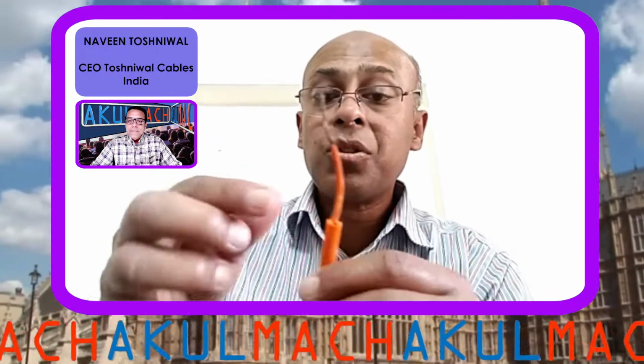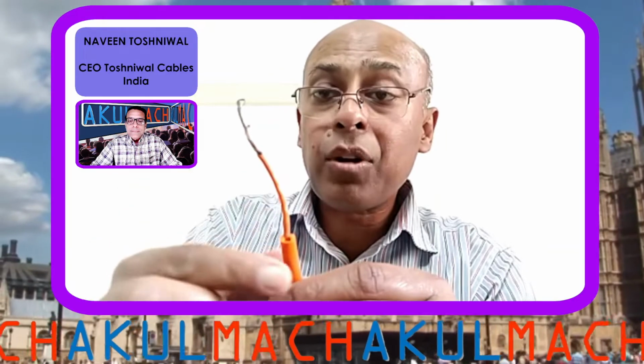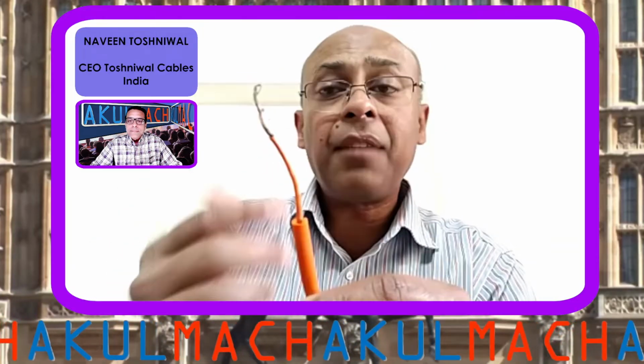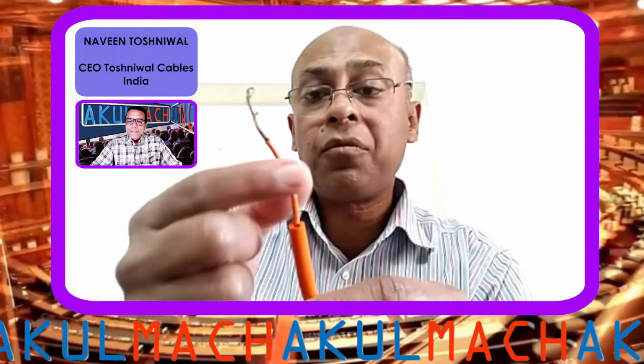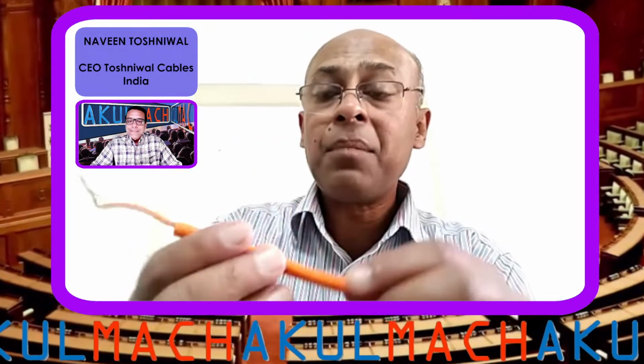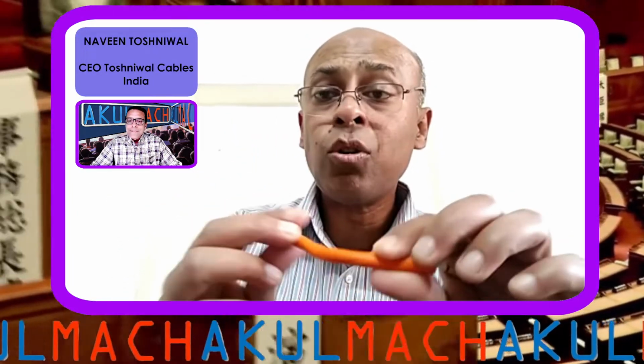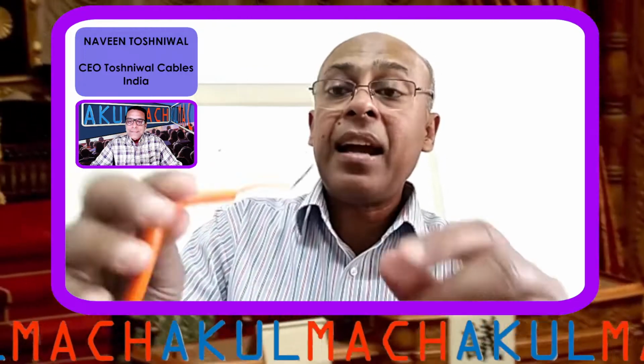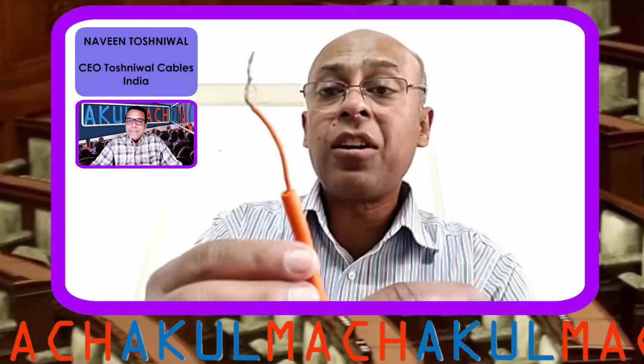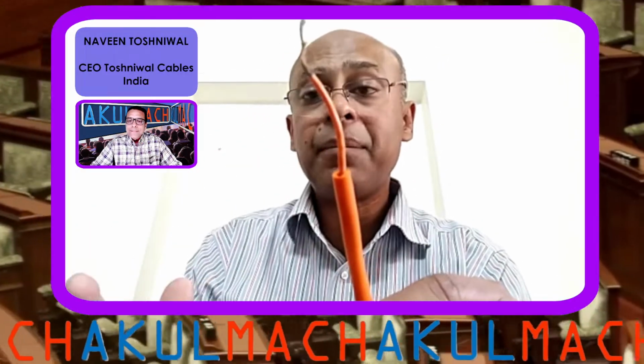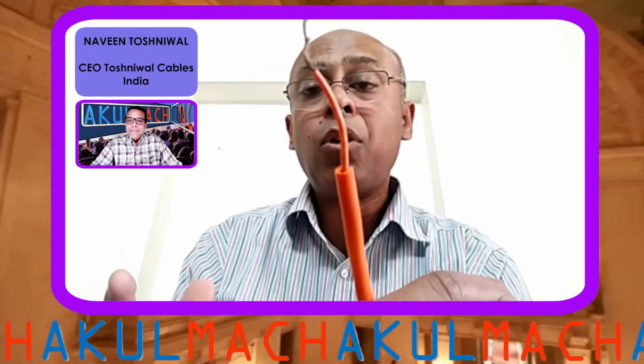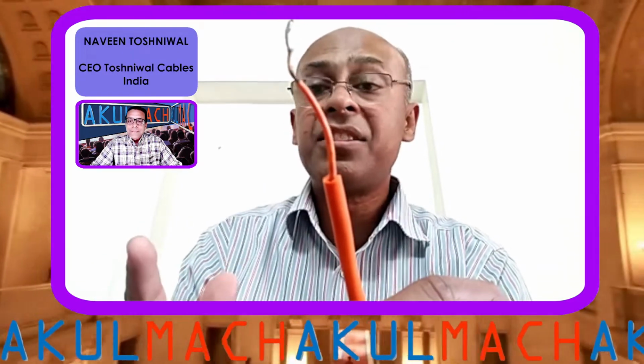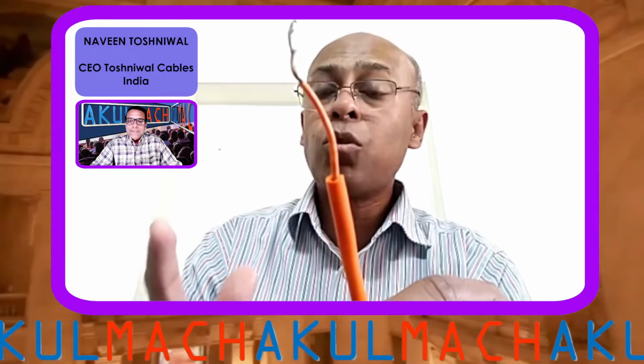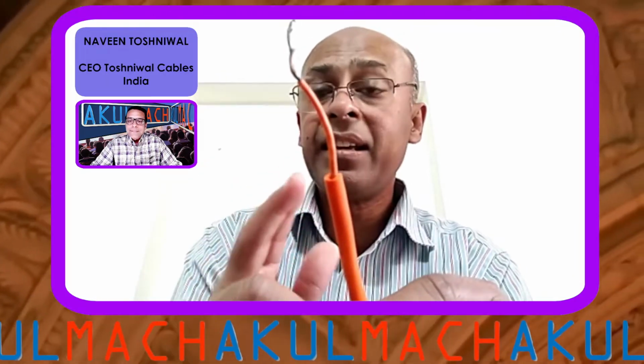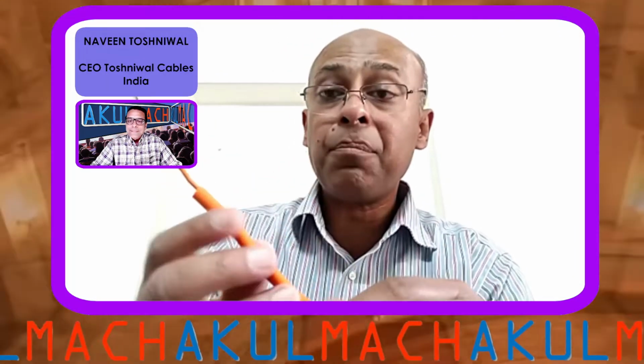So this is one insulation, and for protection, the double insulation is there. Of course, that is as per client's choice if they want one insulation or double insulation. But the most important thing to note here is the flexibility. And another important feature of silicon rubber is that it can withstand temperature of about 150 to 180 degrees centigrade. Of course, Teflon goes up to 260. Here, the temperature rating is lesser, but the important property is the flexibility, which you can see.